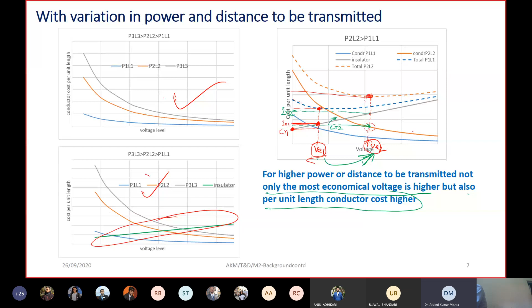If you plot it, the conductor cost is also higher with respect to case 1. What does this mean? If your power or distance to be transmitted is higher, not only is the most economical voltage higher, but also the per unit length conductor cost is higher. This means that when the conductor cost is higher, the size of the conductor becomes higher. So this is a very important conclusion: high voltage lines, for an optimum design, have higher size conductors as well.